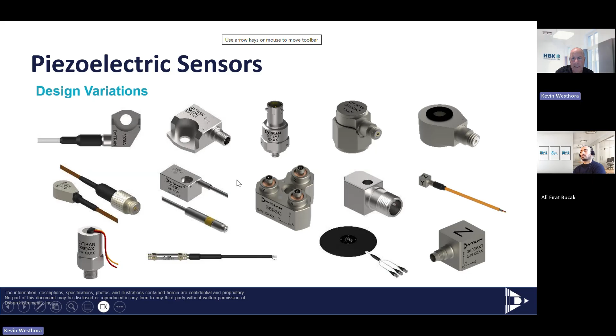All of that goes into the limitation of the upper frequency of the accelerometer. The low end frequency of the accelerometer is dictated by the factory, and it's called the discharge time constant. I don't know if we talked about that. I'm going to show you a graph of it. So DTC is the low end frequency.